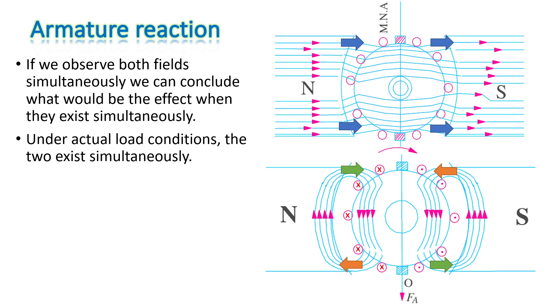At the top north corner, the armature magnetic field is in the same direction as the stator field, so they reinforce each other and the field becomes stronger. At the bottom corner of the north pole, the fields oppose each other, so the armature field tries to reduce the magnetic field there. Similarly, at the bottom corner of the south pole the fields are in the same direction and reinforce, while at the top corner of the south pole they oppose. So field strength increases at some pole tips and decreases at others.